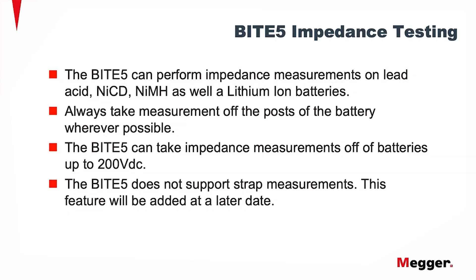The BITE5 can perform impedance measurements on lead acid, NiCAD, nickel metal hydride, as well as lithium-ion batteries. Always take measurements off the posts of the battery wherever possible. The BITE5 can take impedance measurements off of batteries up to 200 volts DC.